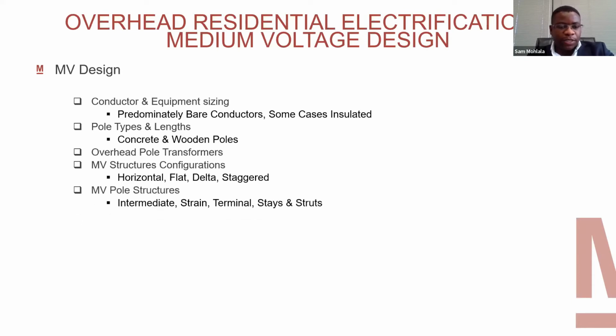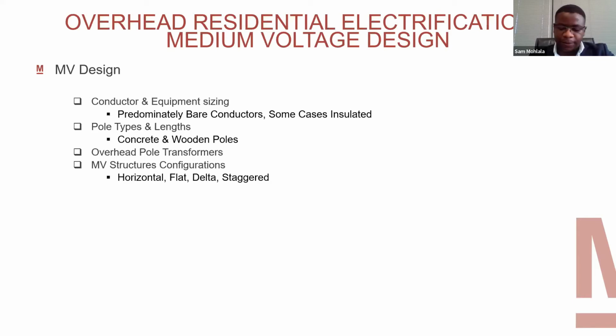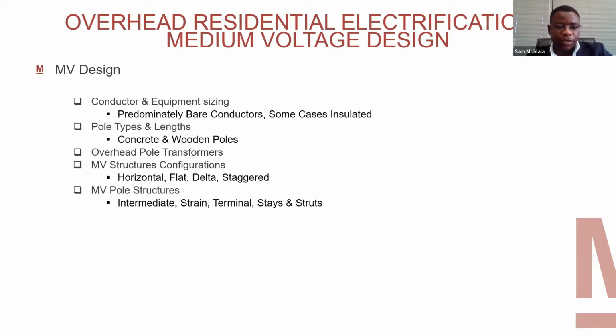MV pole structures include intermediate poles, which have zero degrees deviation, strain poles which can have anything above 5-degree deviation, and terminal poles, which are your end poles. Stays and struts are supporting structures that keep poles in place and prevent them from leaning or tipping over.